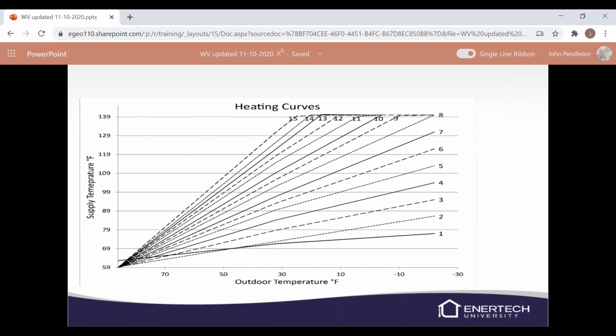This is the heating curve. In the older generation of the unit, we had, I think, 8 curves. Now we've got 15. Normally, I think it may come from the factory at number 3. I'm not positive on that, but I'm pretty sure. So here where we're located in Illinois, it's usually around 3 or 4. But depending on your area is going to depend on where you put your heating curve. And you can change it at any time if you don't like where it's at. You can definitely change it very easily on the HMI.